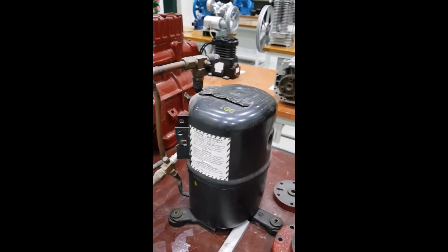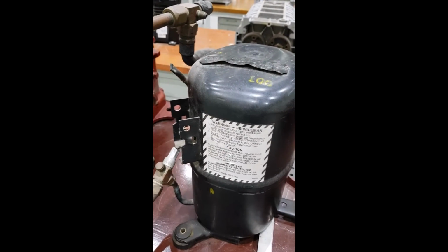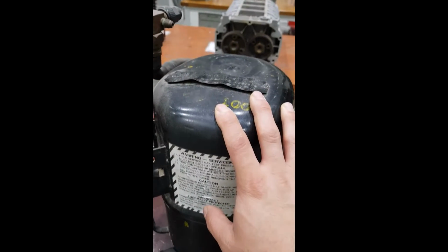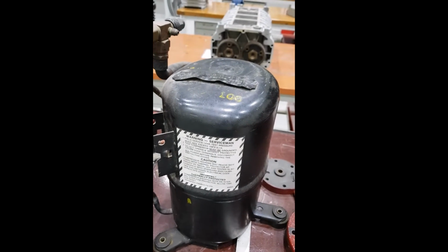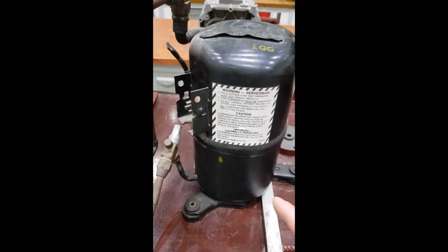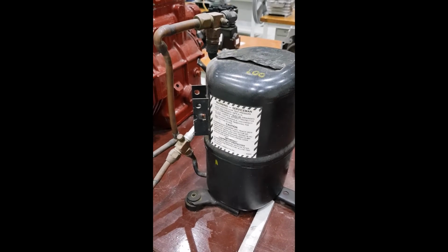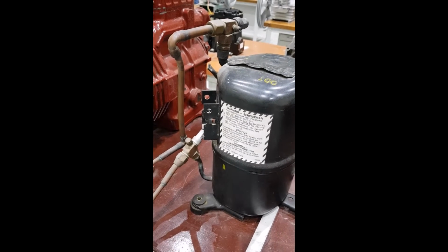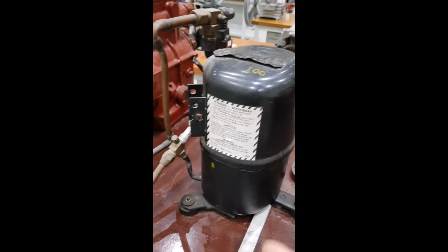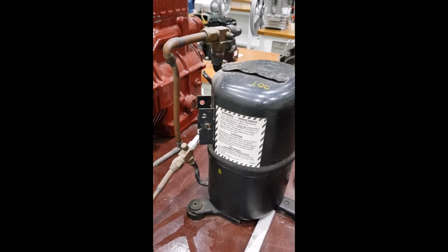The sealed compressor, 99.9 percent I would say, people will throw this one away whenever they finish with it. It has all the parts, a compressor and a motor, coupled together in one unit. This type of compressor is very difficult to maintain, very difficult to bring back to life or to do any kind of maintenance, because the parts are specially welded. It's very difficult even to do the welding again. It requires certain conditions to be done.